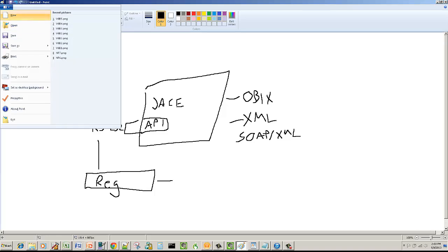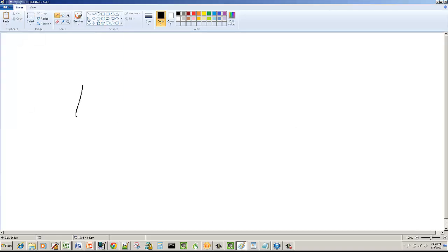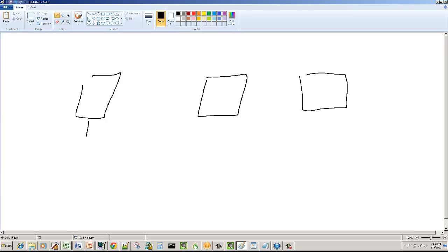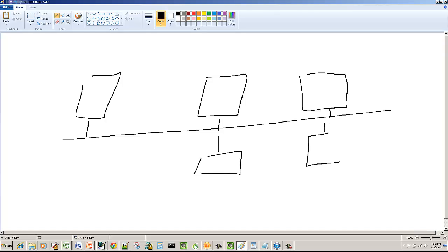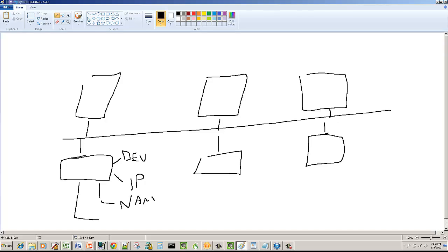A lot of people get into this situation where they buy 3 different systems, System A, System B, System C, and they're all on an IP trunk, and they all have hardware devices coming off that. But then the person who specified it didn't really say, hey, you guys, you need to be smart about this. This system is allotted these device instances. It's allotted this IP address range. By the way, this is your naming scheme. Okay? You're going to use this kind of trunk.